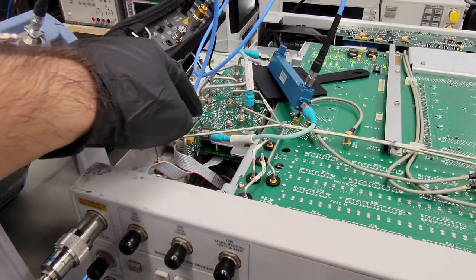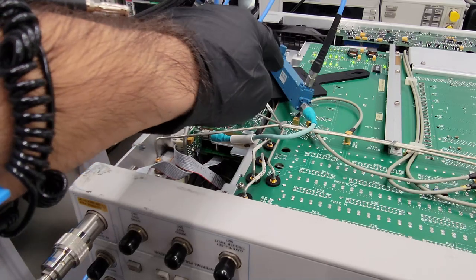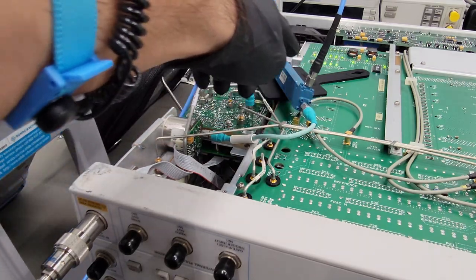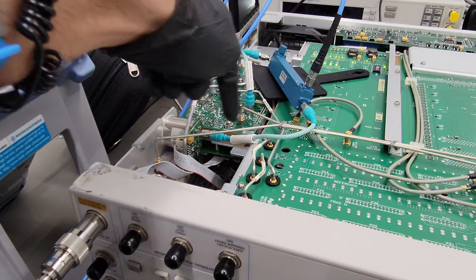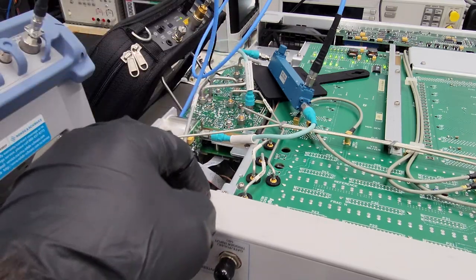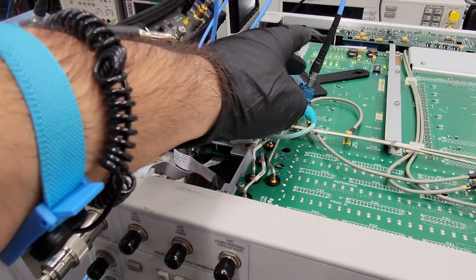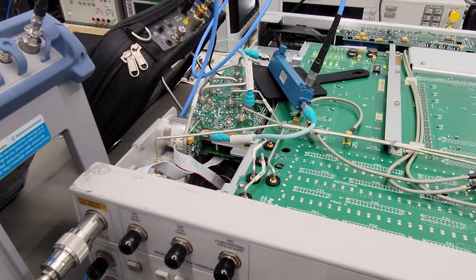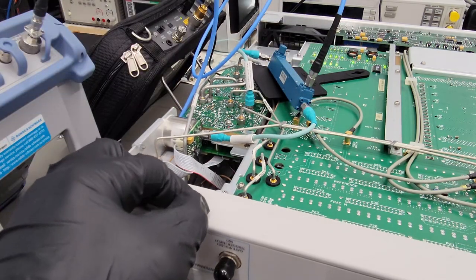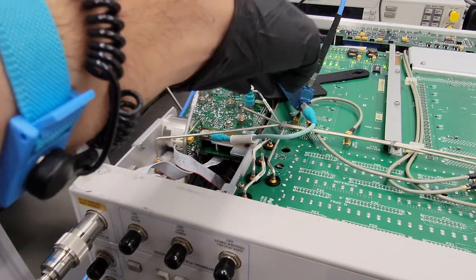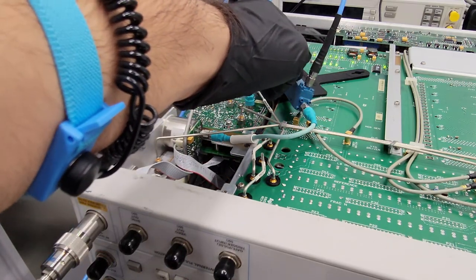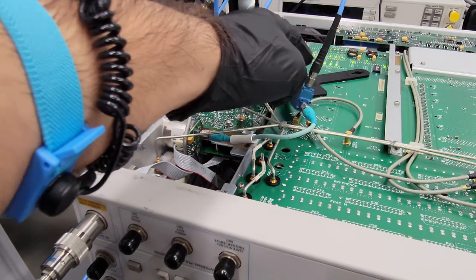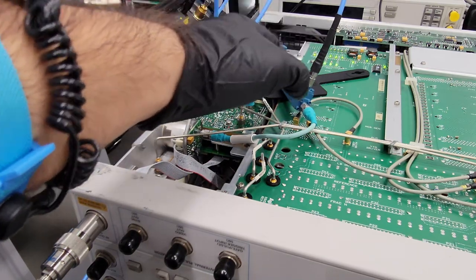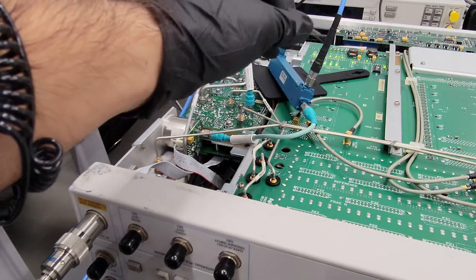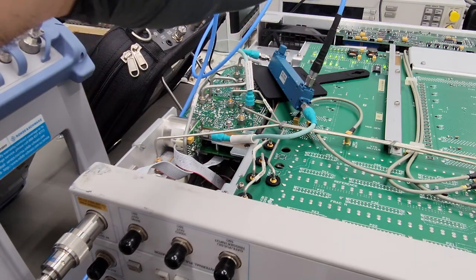And so the signal is passing out of the YIG to the input of the coupler, and the through path, of course, is going to where the YIG would originally just go normally in the instrument. But then we have a 10 dB coupled path here, so I can view the signal that's coming out of the YIG directly. And the amplitude, of course, depends on the coupling factor of the directional coupler here. For this model, it has fairly flat 10 dB of coupling throughout its entire frequency range, plus or minus 1 dB, according to the data sheet.